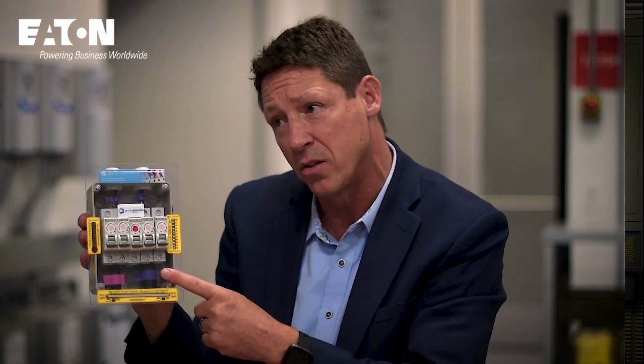The cable manufacturers say at 70 degrees Celsius, that's where the insulation starts breaking apart on the cable. That's number one. Number two, according to OSHA, at 70 degrees Celsius that causes a second degree burn. So it's an over-temperature indicator - if you touch it, it's hot enough to cause a second degree burn. That's why it's set based on the cable manufacturer's threshold.